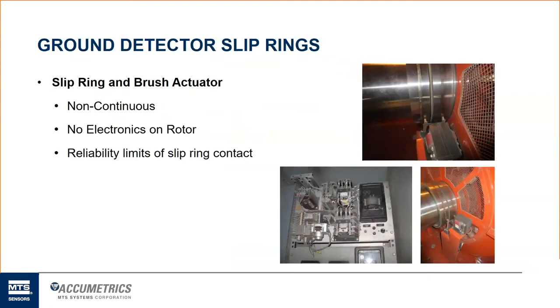So here's the more traditional way to get access to the rotor. It's a slip ring approach where they press fit these slip rings. I don't know if you can see to the right where my cursor is. One of these slip rings is connected to the steel of the machine itself, or rotor ground, and the other one is connected to the negative side of the field. When I talk about the negative and positive side of the field, all that basically means is one side of the field windings versus the other. Those copper bus bars run out on the generator and form many thousands of feet of windings. One side would be referenced to negative and the other side to the positive side of the field. Most classical ground detectors are connected to the negative side of the field and rotor ground.